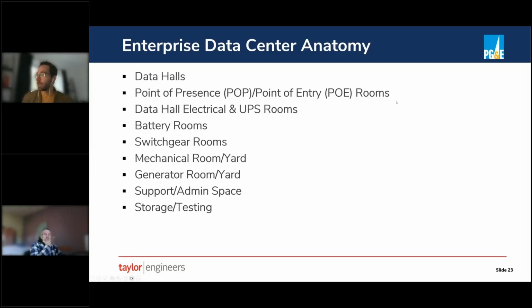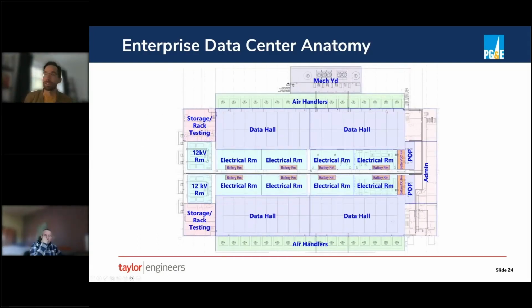Let's look at an example of that. So this is from a project that Jeff and I worked on years ago and has more or less all of these room types. So this particular data center had 4 large data halls, and those data halls were served by flooded aisle air handlers. So these air handlers are just plugged into the side of the building, blasting cool air down the cold aisles in this data center. And we'll talk about the distinction between cold aisles and hot aisles in the later part of the class. Those air handlers were in turn supported by a mechanical yard that had a number of cooling towers and thermal energy storage tank or backup water tank.